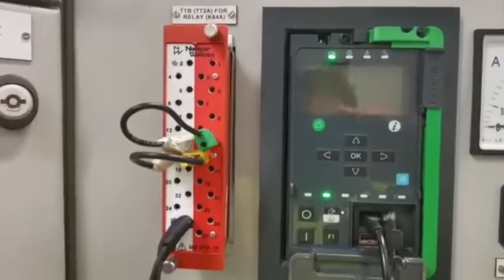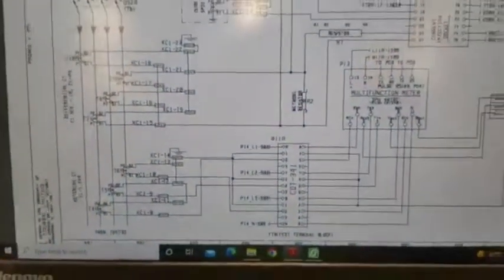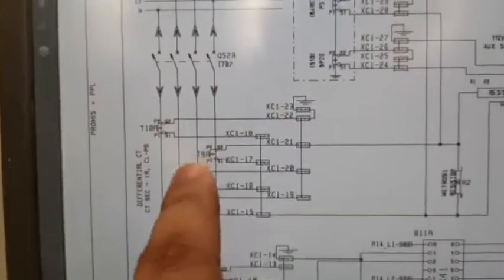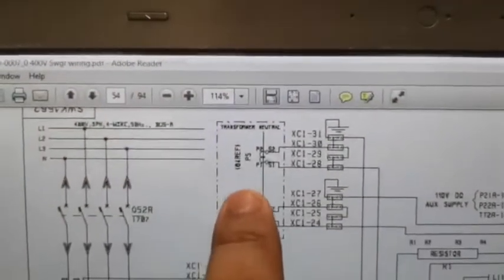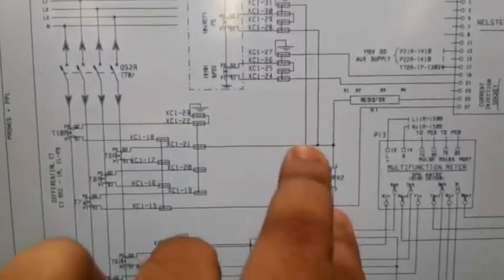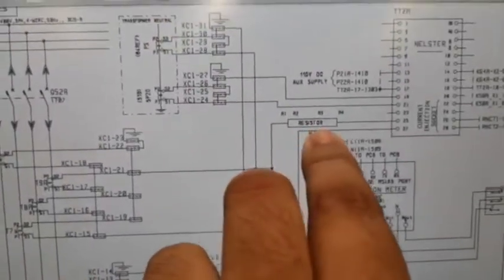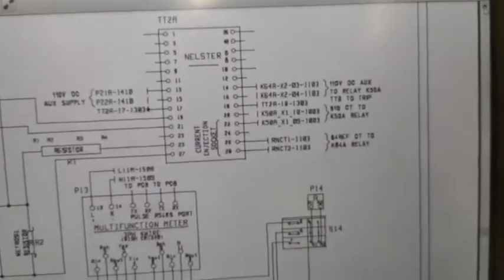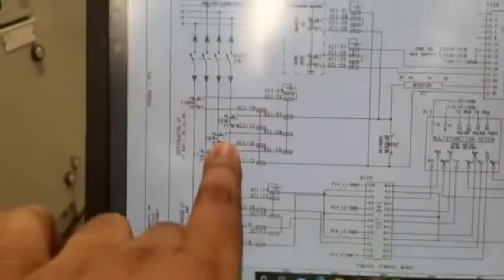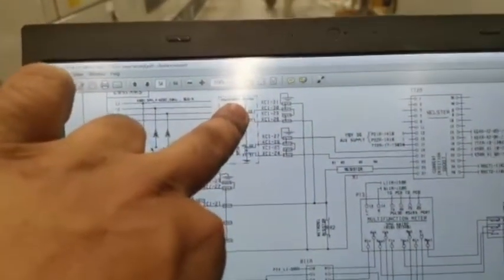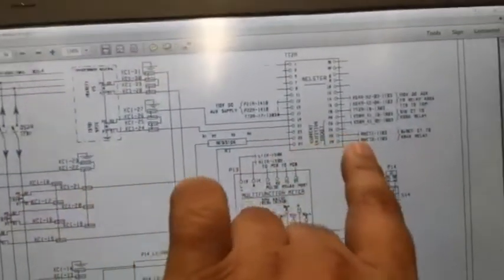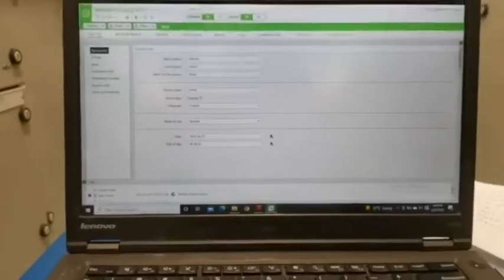Now we are going to see the connections. You can see this is our REF scheme — there are three-phase CTs and a neutral REF CT, all in parallel with the Metrosil. Through the resistor and through the TTB, it goes to the relay. This is the CT connection.